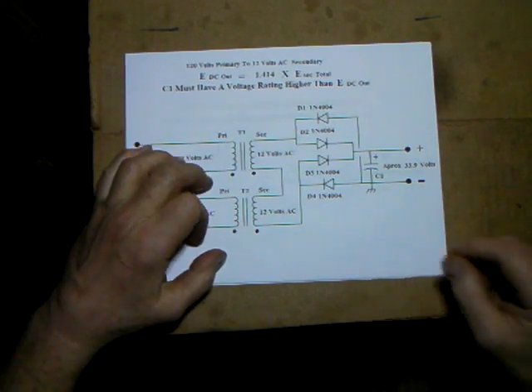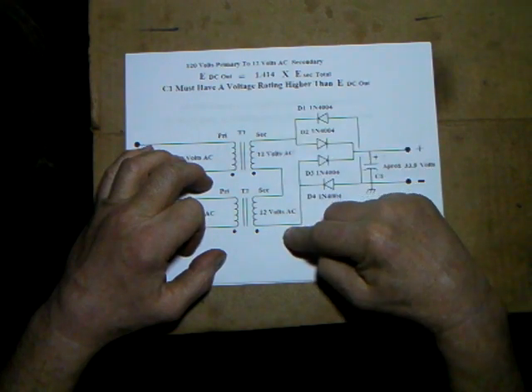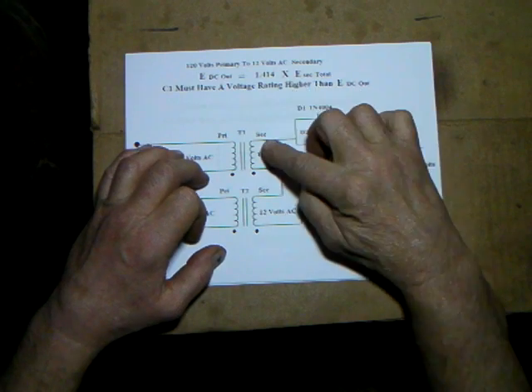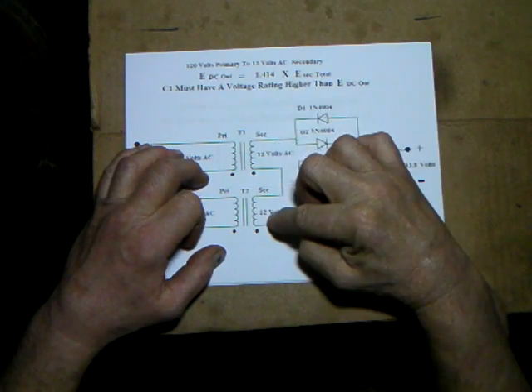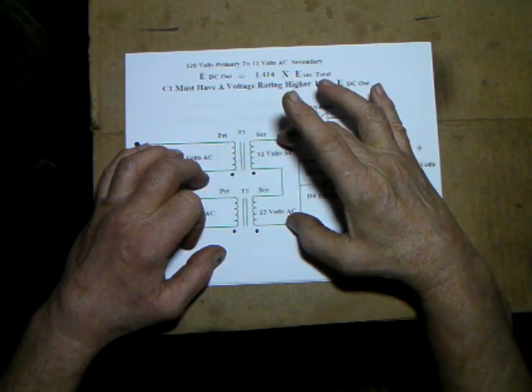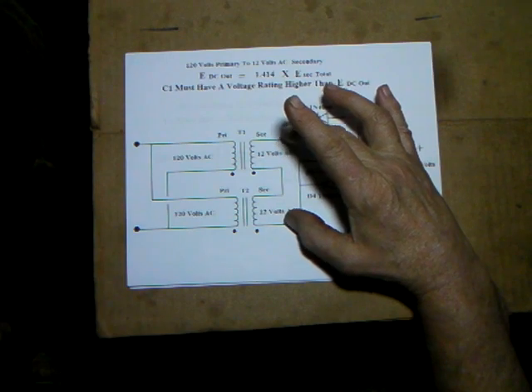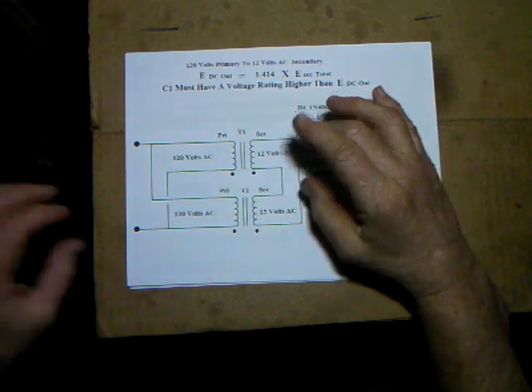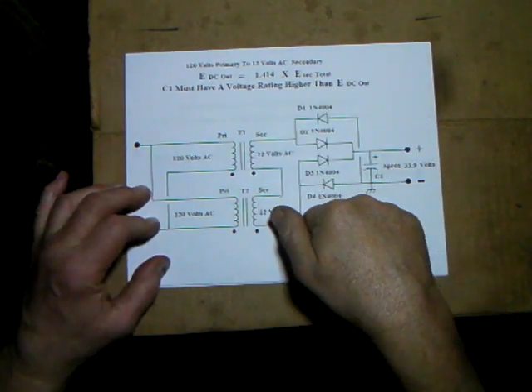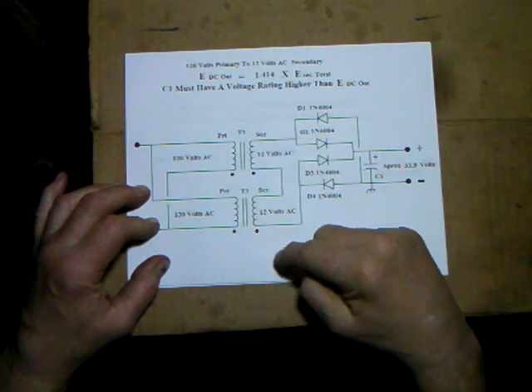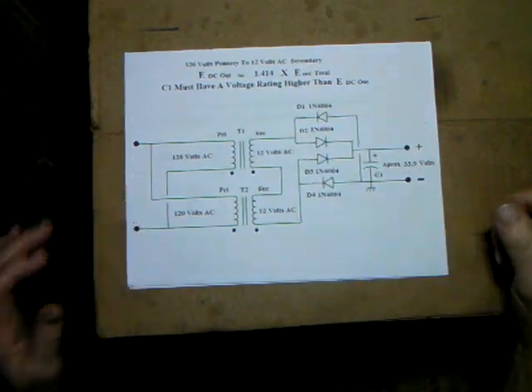What you would do is hook them up in series, then measure the voltage all the way across. Depending on how matched these two transformers are, if it's hooked up wrong, you might see anywhere from 0 to maybe 1 or 2 volts, and you'd know something's wrong. So just flip one of the windings, and that'll put them in series so the voltage adds.